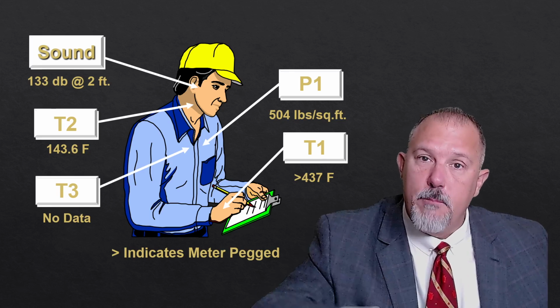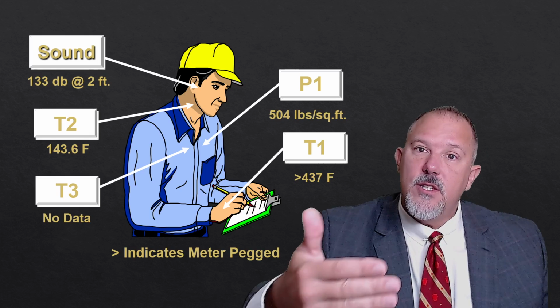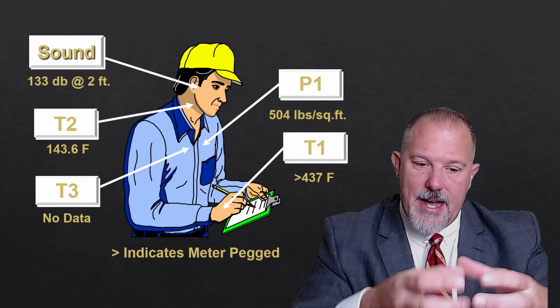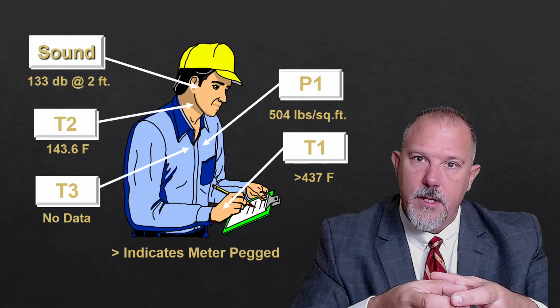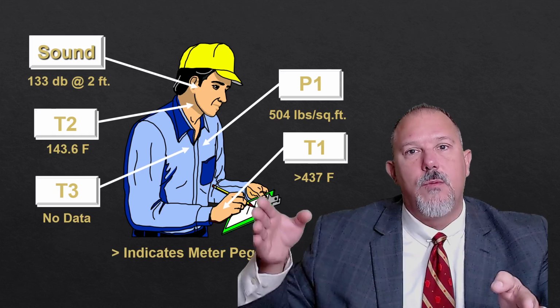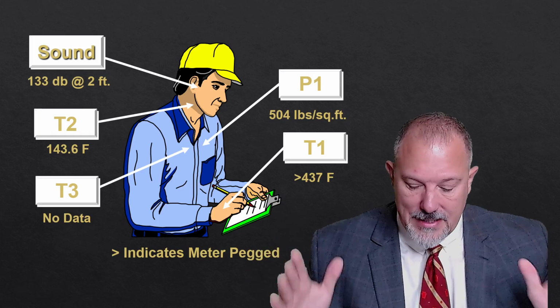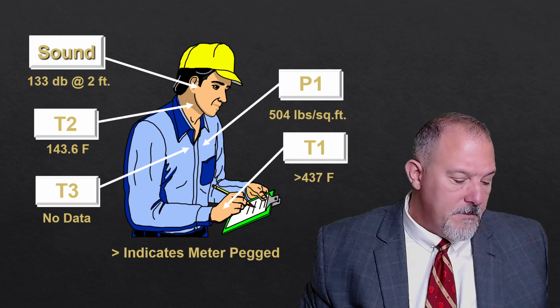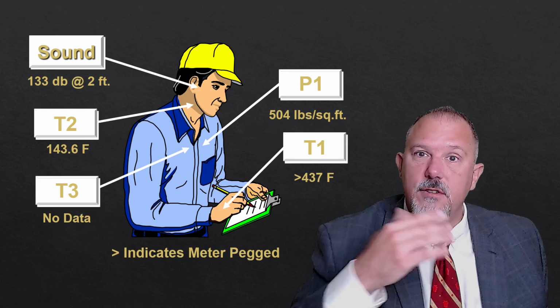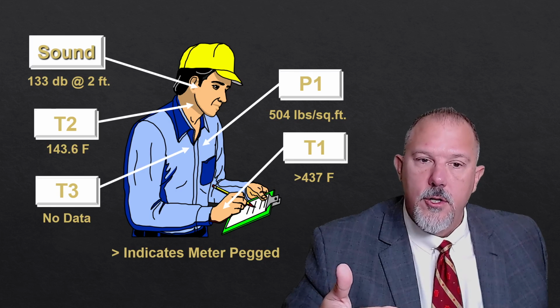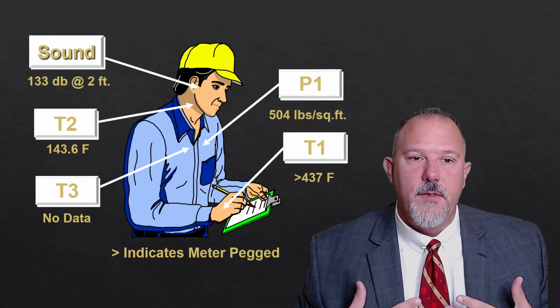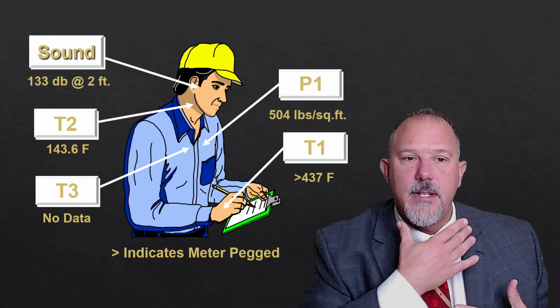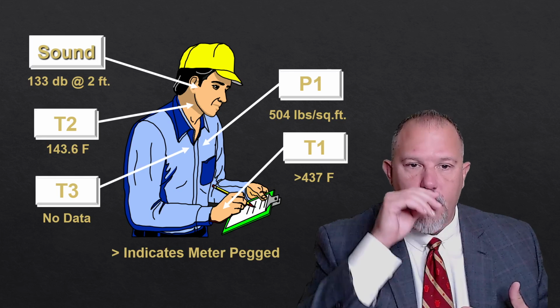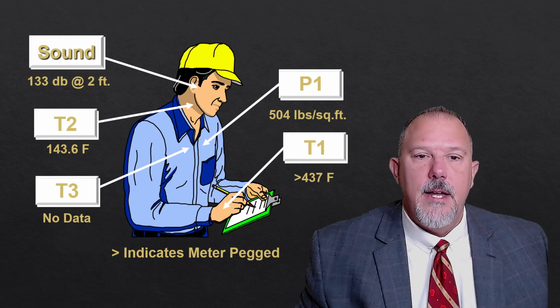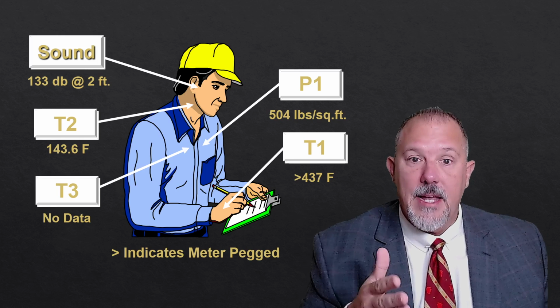An arc flash boundary is the distance away from that exposed, that arcing event, that distance that gets you down to 1.2 calories per centimeter squared. Something that is a survivable burn. So I didn't have any temperature data on the chest. Temperature on the neck was 143.6, and my hands got the brunt of it.